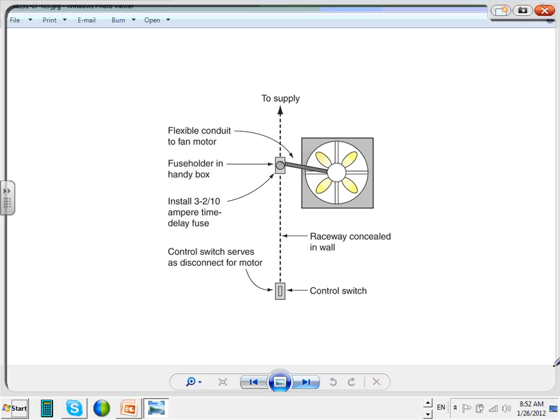Typically in a furnace, most of it. Residential furnaces I've ever seen are pretty healthy sized motors, but they always seem to have snap switches. Snap switches, absolutely, at a fraction of a horsepower. Just grab the switch off the shelf at Home Depot. It's good as a disconnect, absolutely. It doesn't care if it's horsepower rated, not at this size. Naturally, an industrial, more robust switch would be used for 3-phase. I wouldn't put these with 3-phase equipment. We're talking about single-phase equipment.